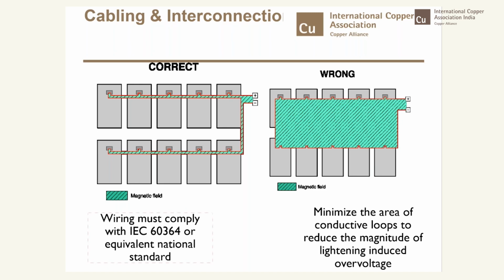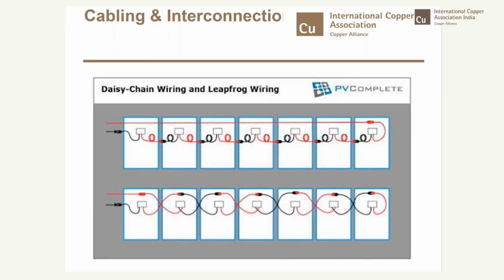Let's move on to the next slide, where I have tried to show you another way of minimizing the magnetic effect. On the top you see what is called daisy chain wiring. The positives and negatives are looped and finally connected. The bottom picture gives you a slightly different configuration. You can see the red wire with the positive and the black wire with the negative. They are cross-linked at alternate modules, so that the magnetic field is nullified and the chances of induced voltages due to lightning, either direct or indirect, are reduced. I think I will share this slide. You can have a look at your convenience later.